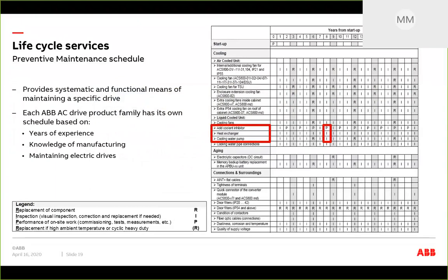Usually it's the fans first, then power supplies and ribbon cables, and then eventually capacitors at about the 9-year mark. Each time, that's helping reset the clock, so to speak, in that life cycle.